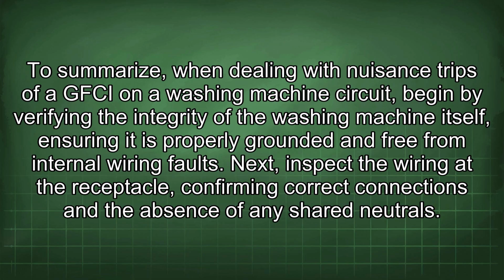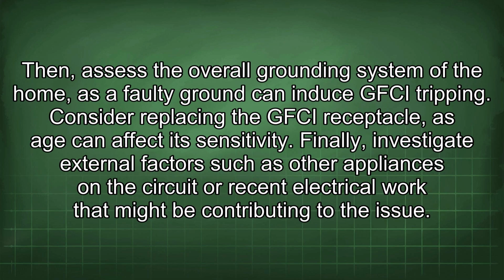To summarize, when dealing with nuisance trips of a GFCI on a washing machine circuit, begin by verifying the integrity of the washing machine itself, ensuring it is properly grounded and free from internal wiring faults. Next, inspect the wiring at the receptacle, confirming correct connections and the absence of any shared neutrals. Then assess the overall grounding system of the home, as a faulty ground can induce GFCI tripping. Consider replacing the GFCI receptacle, as age can affect its sensitivity. Finally, investigate external factors such as other appliances on the circuit or recent electrical work that might be contributing to the issue.